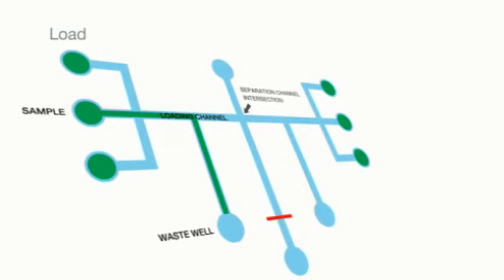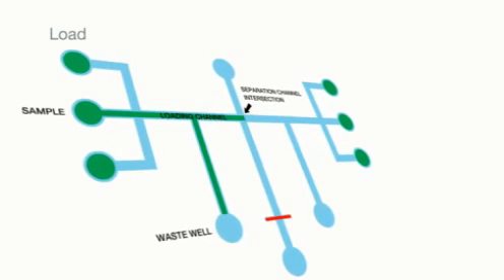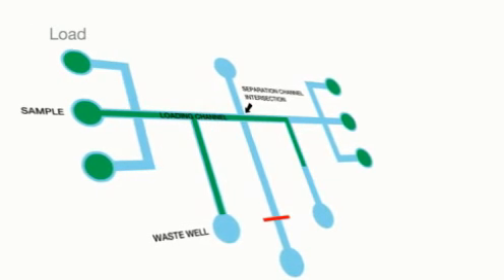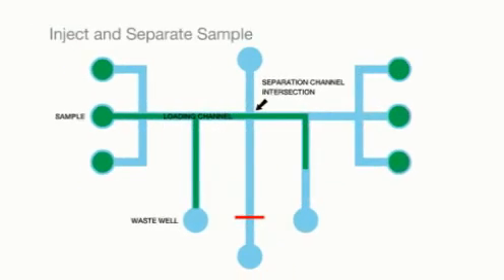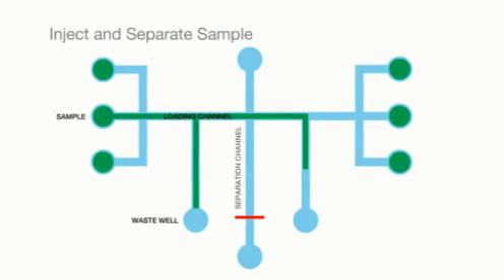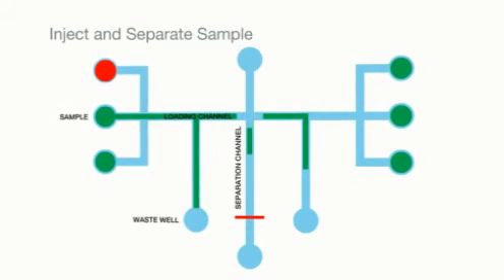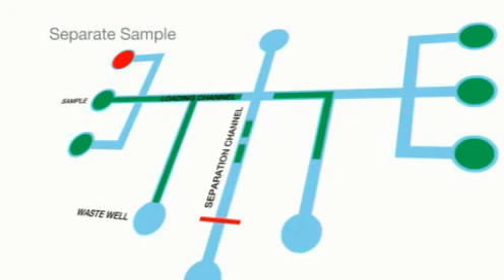The current is then redirected and a portion of the sample is injected into the separation channel, where it begins to separate the sample.